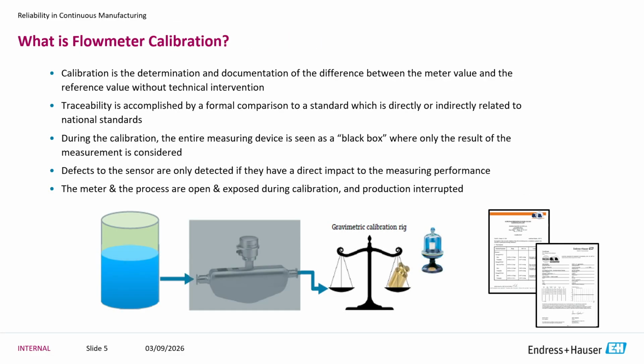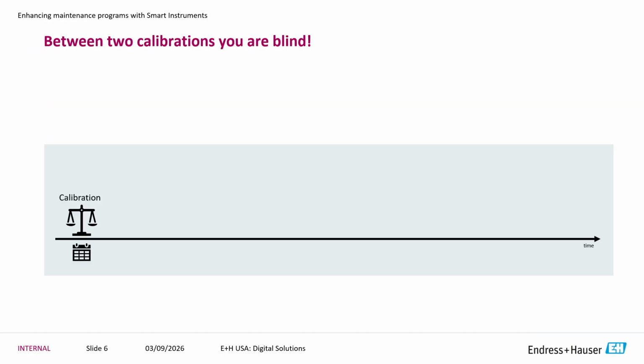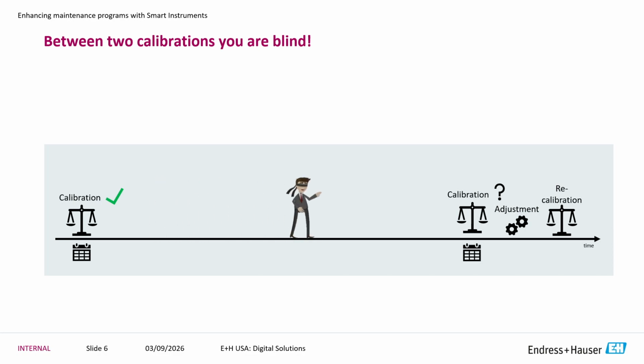But when we look at the calibration, what is the calibration actually doing? Well, it's actually comparing what is being measured in that Coriolis to a known NIST traceable reference, right? But the sensor itself becomes a black box. We just care about what the measurement is showing, right? We actually don't know what's going on with that meter itself. So the calibration is important, but it's kind of blind. So that's the calibration in essence. But in between, if we have the calibration set up, okay, I did it, and then I have an interval of 12 months later, I'm completely blind in between those 12 months.